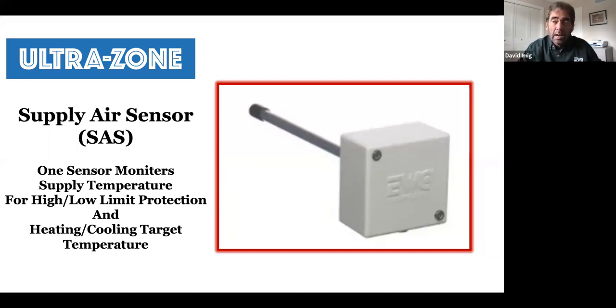installation, and you can mount that rather than the outside and deal with the sunlight and indirect temperatures and so on. You can, in snowfall, put that right inside the sill plate on an incoming fresh air damper, excuse me, a fresh air duct, or a fresh air intake for either my water heater or my furnace. It allows you to cut that probe to a length that will fit in any of those choices.